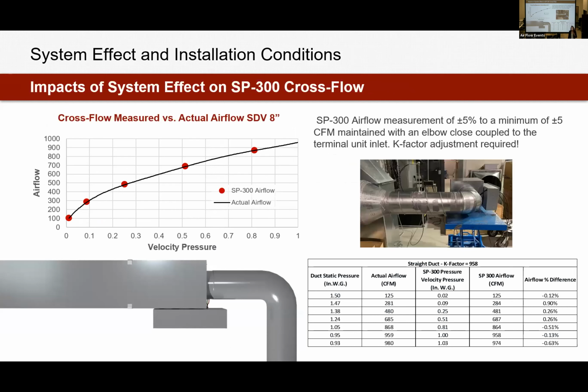So what can we do about it? Well, I kind of alluded to this, but the crossflow sensor is kind of your best friend in a scenario of poor inlet conditions. Now, this is only looking at the inlet, right? Because we don't have a sensor on the discharge. But in our lab, this is what this image is here on the right. In our lab, we've actually mocked this up and tested what are the effects of putting a hard 90-degree elbow directly on the inlet of a terminal unit. The crossflow sensor did an almost perfect job at compensating for it. We can see the actual airflow versus what the crossflow sensor is measuring in that graph there. We were able to maintain plus or minus 5% of that reading, even with a poor inlet condition, even with that hard elbow. There was some adjustment required on the K factor.